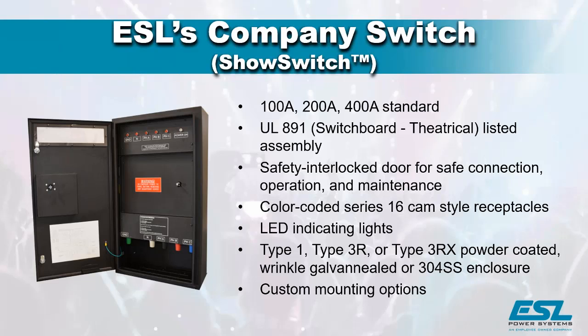We can make the unit in different environmental types, of course type 1, type 3R, type 3RX. Just an interesting note is that these cannot be 4X. I do see them specified that way sometimes, so we have to discuss it, because they have openings on the bottom to allow for portable cables. Therefore they can never truly be 4X, since they would fail a hose down test. But they're built to 4X standards, with continuous seam welding all around, and a very hardy powder coat on there too.